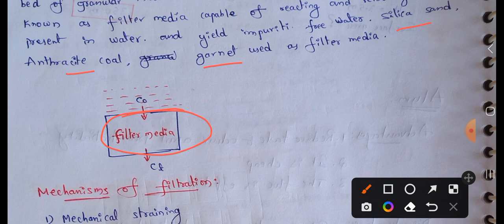The filter media layer is approximately 90 cm to 110 cm in thickness. The top layer can be 2 to 3 cm. The fine particles accumulate at the top layer capturing impurities. When water passes through, the sand is cleaned during the cleaning operation, and the filter medium is replaced.